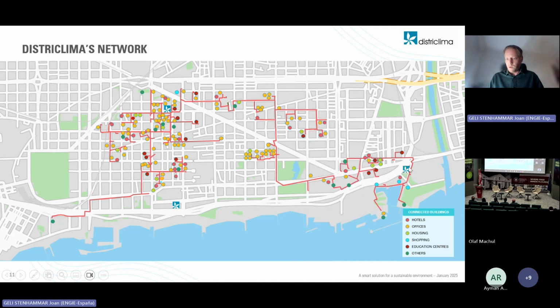So the first plant was the Forum plant, which is the one I'm showing just here. It's in a strategic location because it's very close to the harbor, where we have a seawater captation that allows us to increase the performance of the chillers. It's also placed just nearby the waste incineration plant of Barcelona. When DistriClima was conceived, the idea was to recover the excess heat that was previously being thrown to the Besòs River. So the idea was to collect this heat, not only to satisfy the heating demand, but also to use it to produce cooling capacity thanks to absorption chillers.